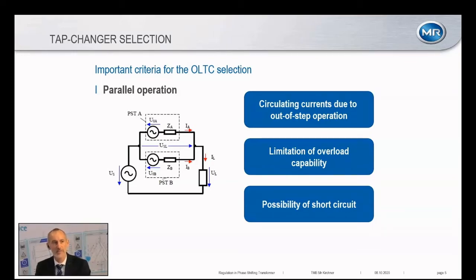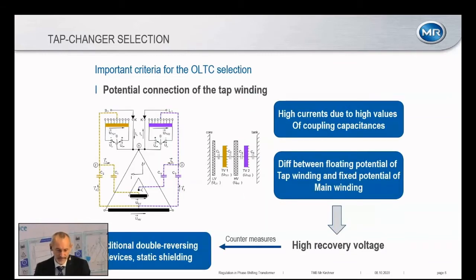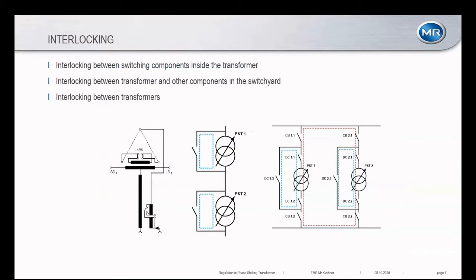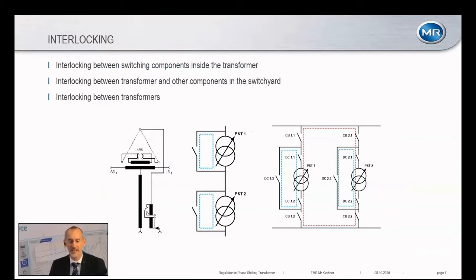We ask customers whether parallel operation is planned and what the circulating currents are, so we can account for them. Another point, especially for single core designs, is the potential connection of the tap winding. There is a special single core design where very high recovery voltages appear on the pre-selector — in some cases so high they cannot be handled without shielding on the regulation windings. This must be considered up front, not at the end of the design stage.